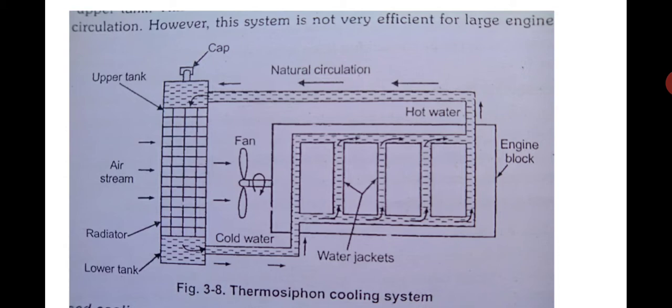The hot water goes up due to natural circulation. Here there is no pump, as I said. As the temperature of water increases, its density decreases and it becomes lighter and goes on the top. So this is the principle on which it is working. The hot water comes to the top and goes to the radiator.